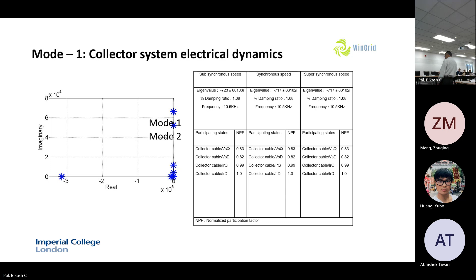This is the collector cable voltage and currents, right? So they may predominantly participate. The 30 kV cable voltage and currents are more dominant in these sort of modes around 10 kilohertz. So for other modes, if we see here again at different values of wind speed, there are the wind turbine generator stator current and also stator voltage that participate into this mode.